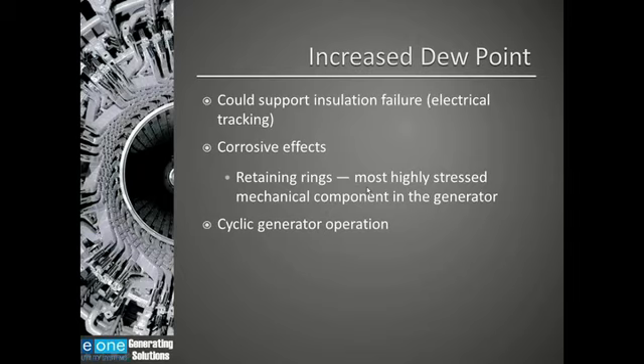Now, cycling a generator will not cause dew point to go up. However, if I'm cycling a generator, what I'm doing is heating and cooling the generator. And what will happen on a base load unit, for instance, where the unit may be warm all the time, you're less likely to have condensation form. But on a cycling unit where you're bringing a generator down and it's sitting for a while, there is a possibility that you could have condensation form in the generator. Some other points about dew point.